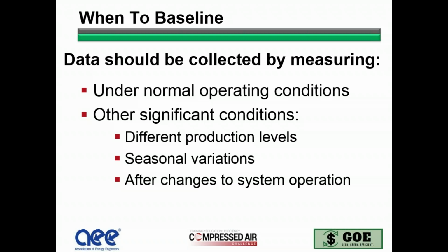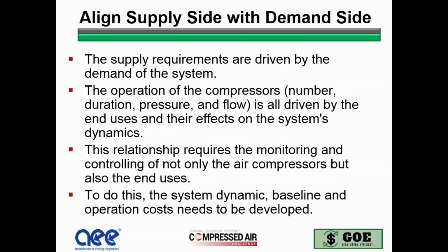Data should also be collected under normal operating conditions. It should also be collected under other significant conditions as well. We want to look at different production levels. We want to look at seasonal variations, and then we want to look at changes to the operation, whether you've added equipment, taken equipment away, or changed processes. You really want to look at that before and after. And the real key for why you want to do that is because you want to align the supply with the demand.